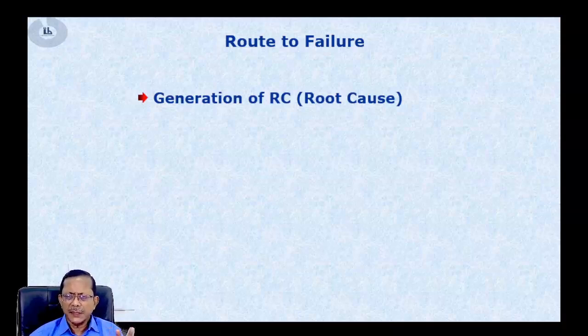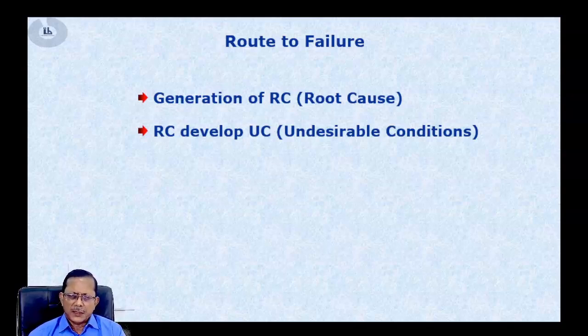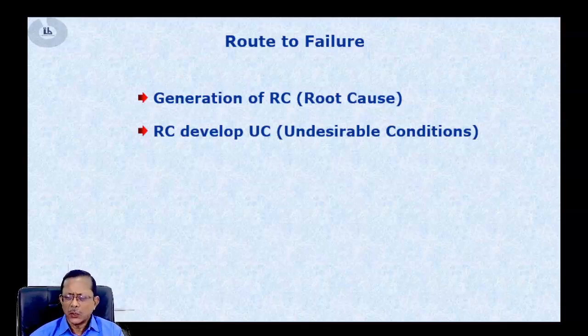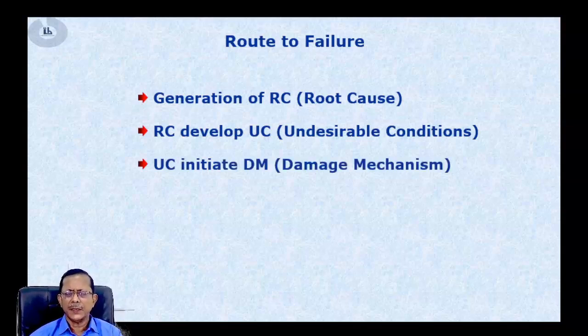When there is a root cause, it creates an undesirable condition in the system — high gas temperature, high steam temperature, correspondingly high metal temperature; high flue gas velocity that increases erosion; or on the water side, chemical parameters not maintained properly, leading to a corrosion condition.